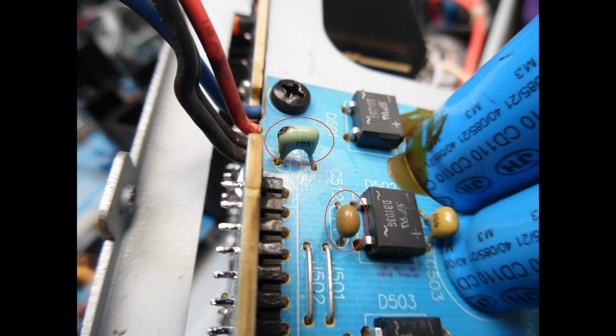Looking at it from the power supply aspect, there was another issue identified, associated with these small 100 nanofarad capacitors. The one near the small bridge rectifier, with the red circle around it, capacitor C512, had failed short circuit. The other one, where you can see a burn mark right on the corner, didn't go short circuit.